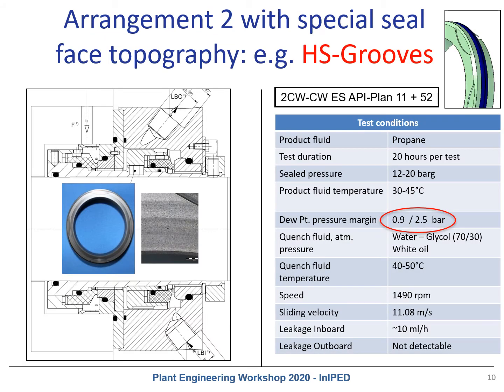Low vapor pressure margins may result in a dry running risk. In order to generate a more stable lubrication film and provide additional cooling, seal faces are modified by different face topography. A typical example is a dual seal in tandem arrangement in combination with piping plan 11 and 52, running in propane at low vapor pressure margins of 0.9 or 2.5 bar. In this case, the face topography used is called HS grooves — hydrodynamic grooves machined in one sliding face to improve liquid lubrication.